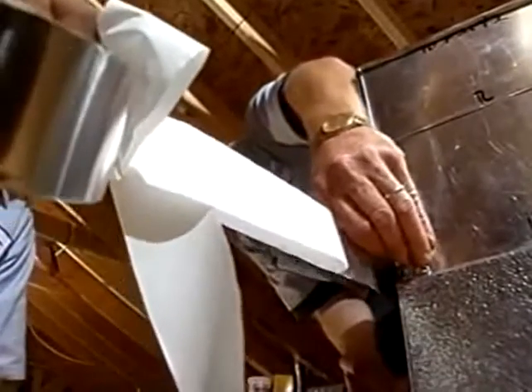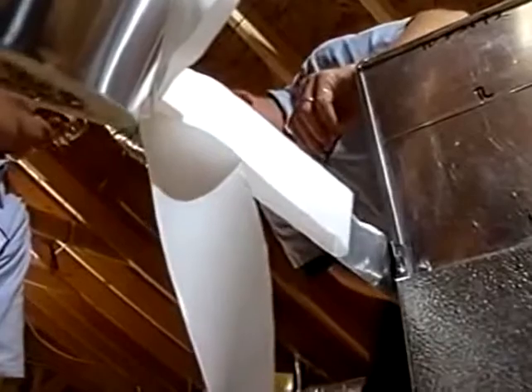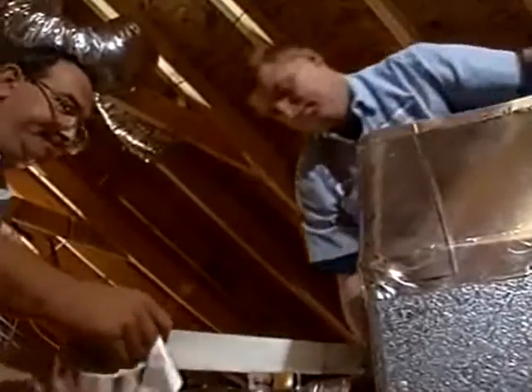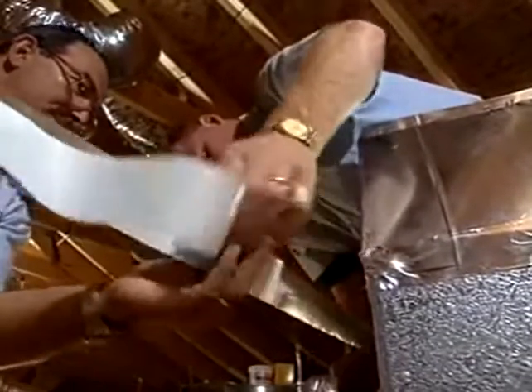Some subcontractors have been sealing ductwork for years. So why then do so many systems leak? The simple answer is that ductwork leaks because people put it together with duct tape, and duct tape doesn't work. It works for a lot of things, and it's great stuff, but it doesn't work on ducts. It'll lose its adhesive properties, it becomes dried out and brittle. It doesn't deal well in high moisture situations such as you may find in a crawl space or even up in an attic in a hot, humid climate.